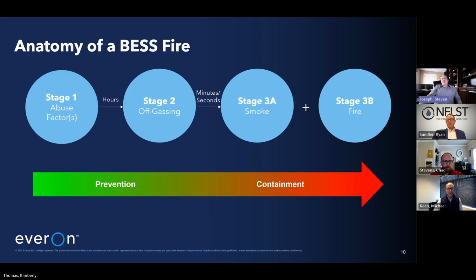So, it's really, as the polls are showing here, advanced detection technologies that in this stage of development include sensors such as mechanical sensors for the detection of impact, temperature, thermal imaging detectors to detect thermal anomalies at the point of interest, and humidity detectors, which are typically integrated as part of the battery management system. And then also water leak detectors. Something as simple as a water leak detector could have prevented a known fire that occurred. It's relatively inexpensive technology, but very effective, in a situation that involved the battery and could have been avoided with something as simple as a water leak detector. And then also gas detectors such as SO2 for the corrosive gases, air quality monitors for dust, and of course, very early warning smoke detectors to detect the issues before the fires progress.